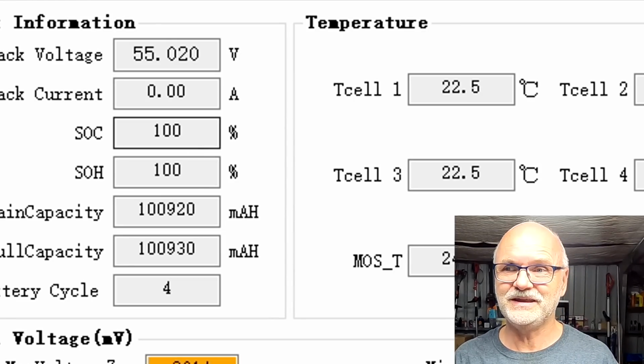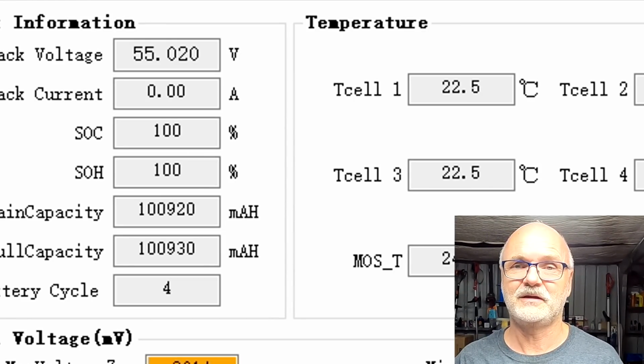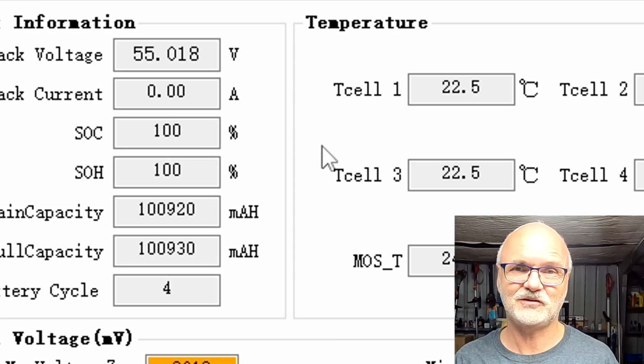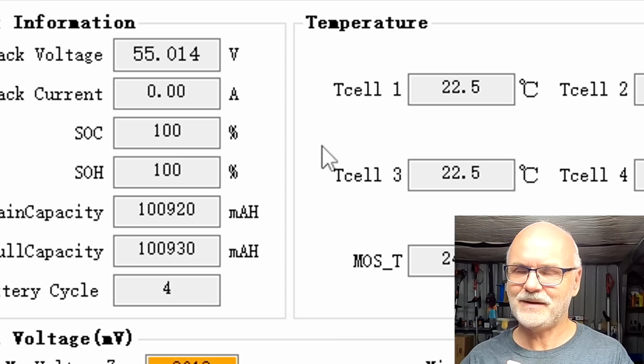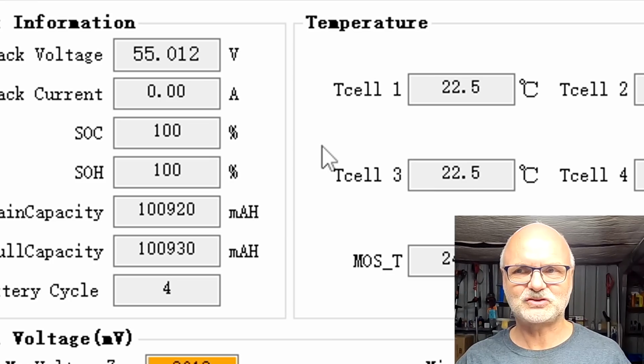And this is obviously a problem which goes through all these BMSs, starting from the Seplos BMS, which needs an overvoltage protection trigger to reset to 100%. The same for the QSO battery with the Tagaluma BMS, and now with the Pace BMS in the Jakiper battery as well. They all need to trigger the overvoltage, so you need to go into the extreme of 3.65 volts with one of your cells to actually reset to 100% state of charge. And none of these BMS manufacturers get this right. Your state of charge showing by the BMS and your inverter and your system will always be around 91% only, even when the battery is fully charged.